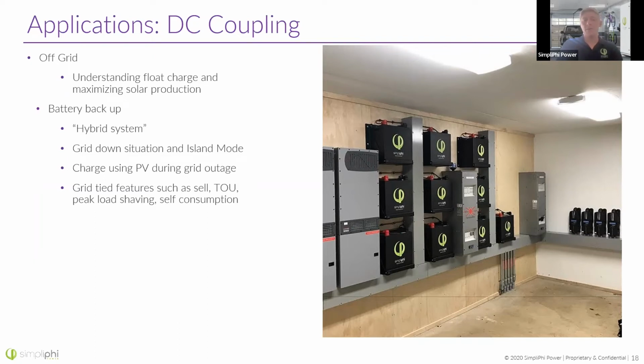In a battery backup system, so a grid-tied system, this is often known as a hybrid system. So you've got the grid and the batteries, but if the grid goes down, your equipment can disconnect from the grid and function in island mode. So keeping the DC coupled PV array on is no problem for that inverter. The DC coupled PV is not even going to notice that the grid ever went out. You're able to easily sell to the grid if the grid is on. You're able to easily separate where your power is coming from.